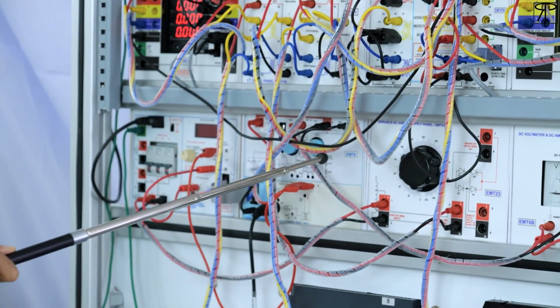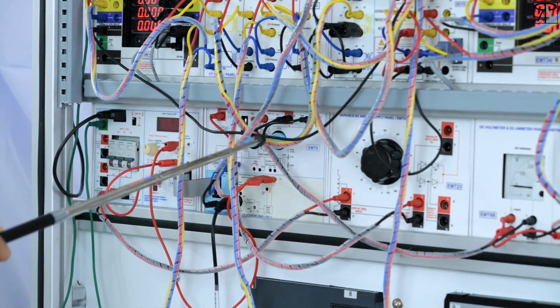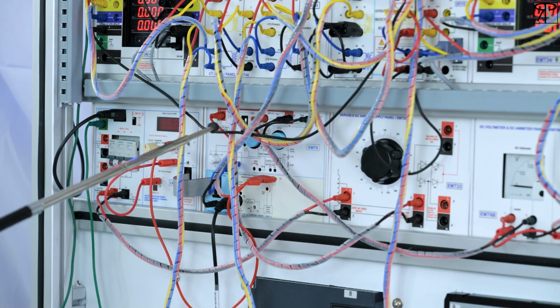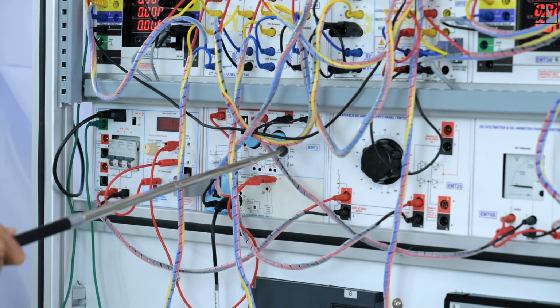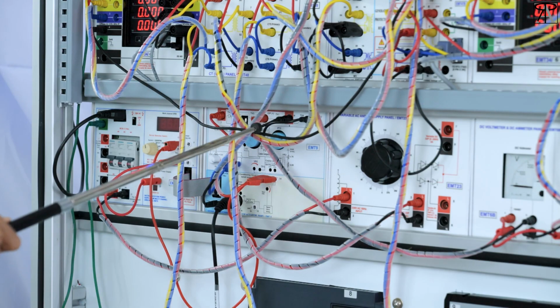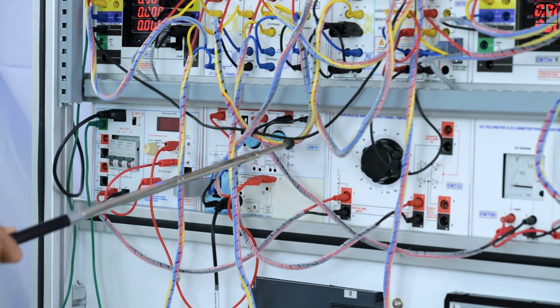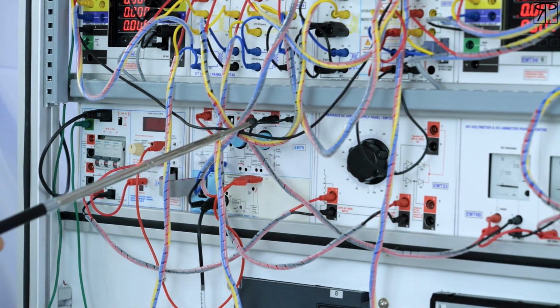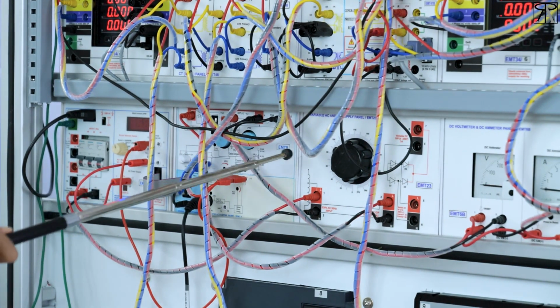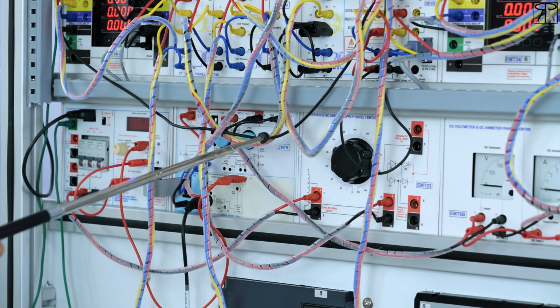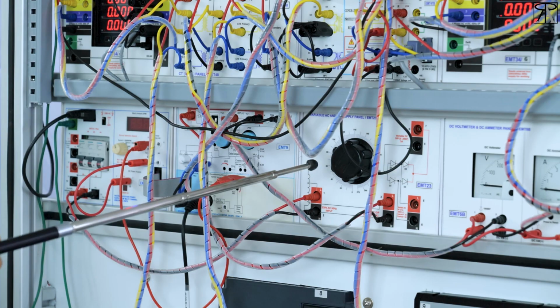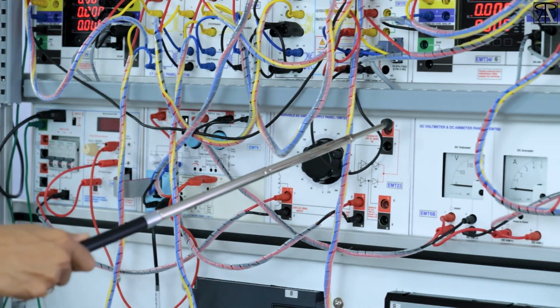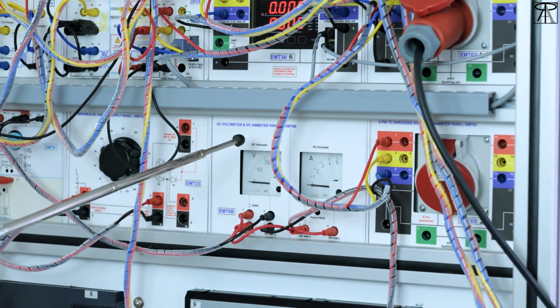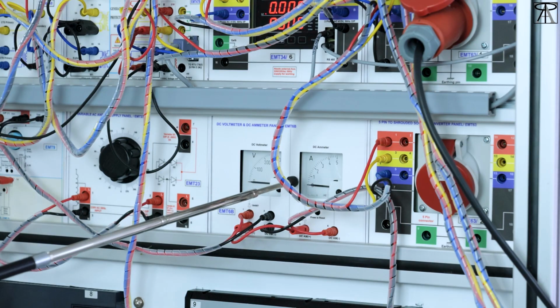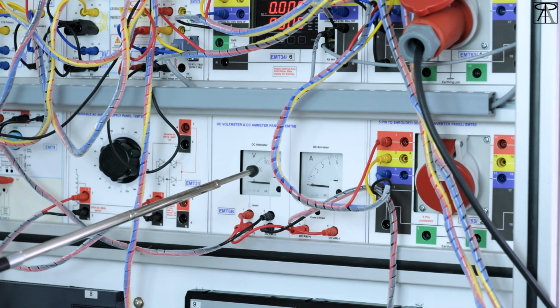This is for the generation, as any generator needs excitation voltage. For excitation voltage, we use EMT 8 and EMT 9. EMT 9 output will come 0 to 180 volt DC, and the input is 0 to 230 volt AC. We are using AC through the dimmer panel, and the output will come. We can control it smartly, including lower voltages. For that purpose, we have used the EMT 23 dimmer panel. This is the DC voltmeter ammeter panel for measurement of DC voltage and excitation current, to monitor while making experiments.